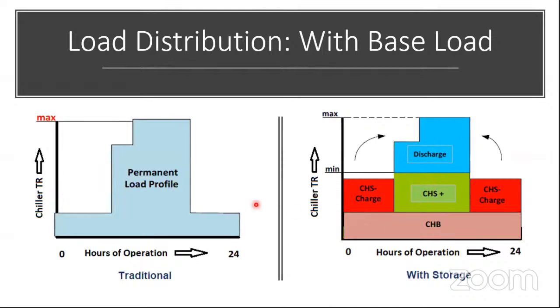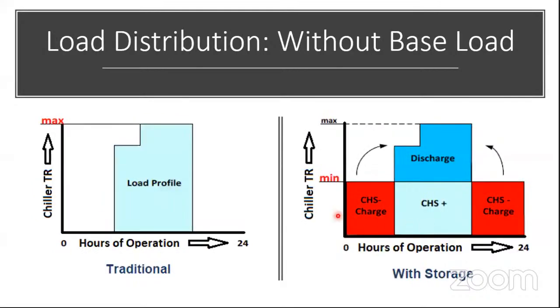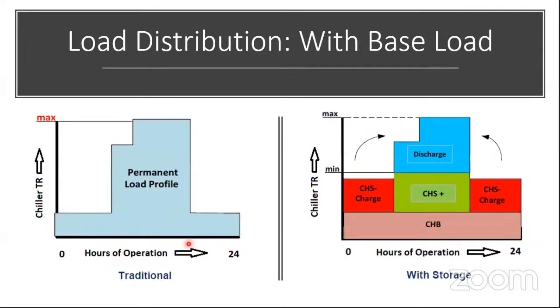However, in the next load profile, we will see why it is required. Because here, you need to have a base load to be able to make a profile like this. And because if you separate your base load, which is already taken care of by a water chiller, you have only this much load to be taken care of, and that is where you can implement your brine circuit.